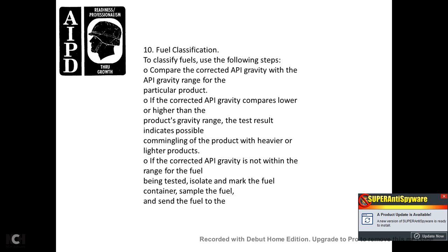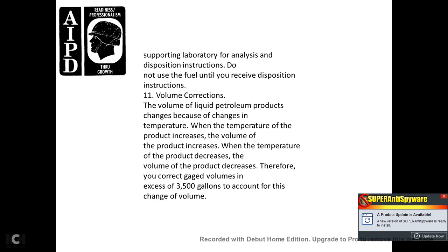10. Fuel classification. To classify the fuel, follow these steps: compare the corrected API gravity to the API gravity range of the particular product. If the corrected API gravity is lower or higher than the product gravity range, the test results indicate the possibility of commingling with heavier or lighter products. If the corrected API gravity is not within the range of the fuel being tested, isolate and mark the fuel container, collect a sample, and send it to the supporting laboratory for analysis and disposition instructions.